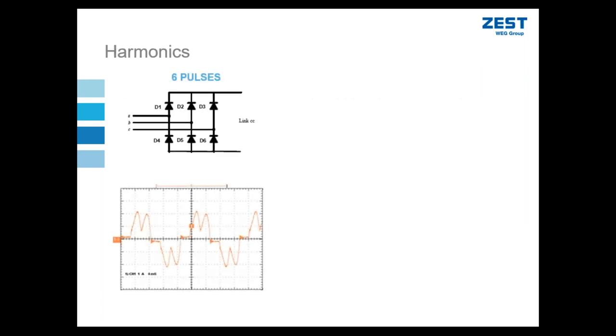All right, so let's look at some actual measured waveforms for the different diode rectifiers that we were discussing earlier. If you measure the current in one phase on the input of a six pulse rectifier, we've shown theoretically what it looks like. This is an actual measurement. It gives us a typical THDI, that's total harmonic distortion current, of about 36%. It depends on a few things. It depends on if I'm putting in an input reactor to reduce this. It also depends on the load we saw earlier.